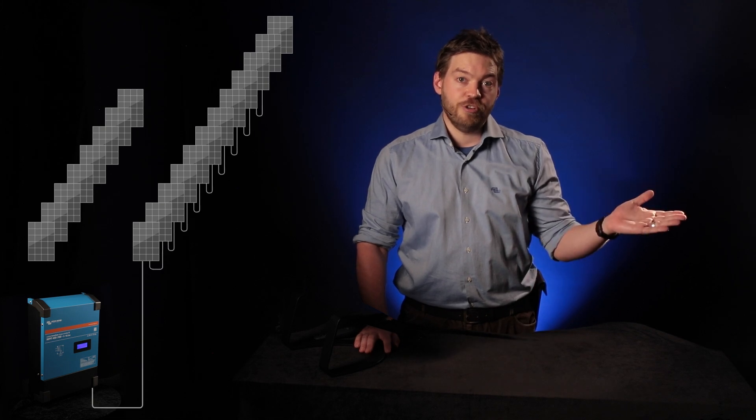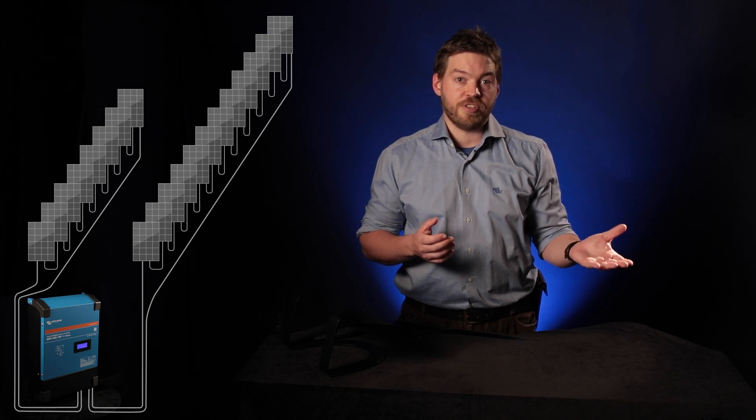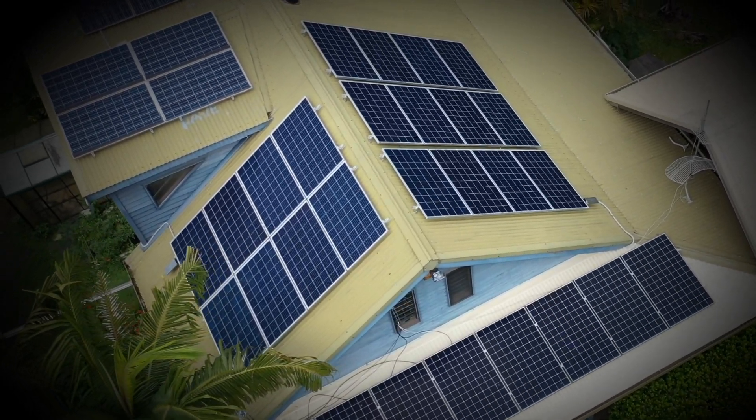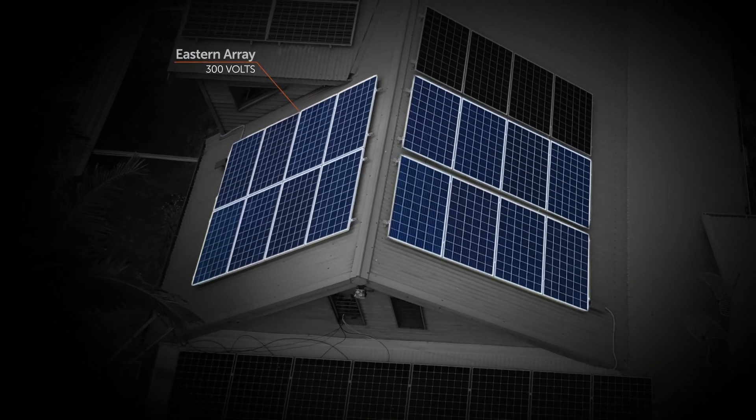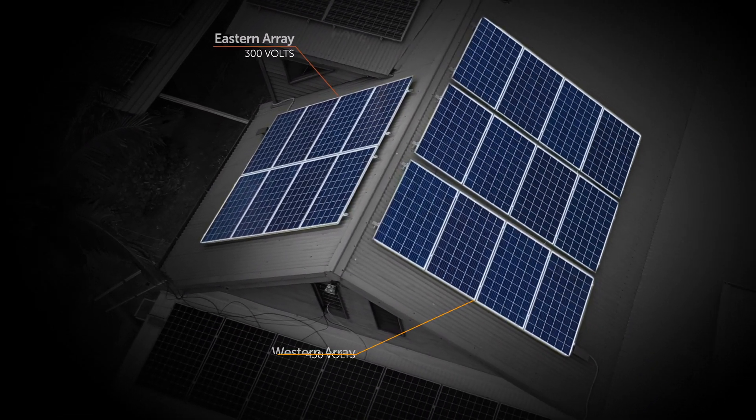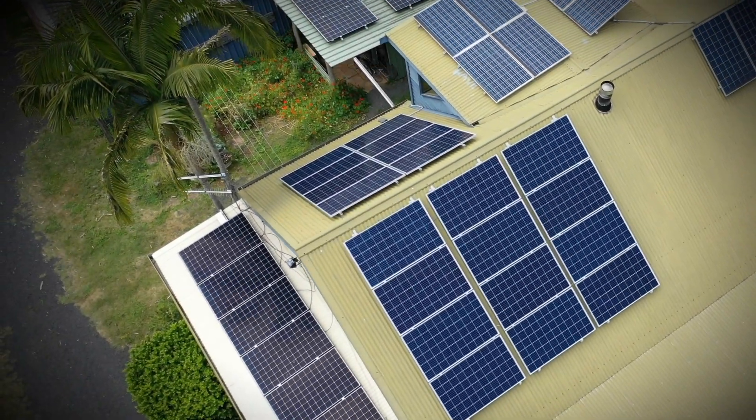Another big new feature of the MPPT RS is independent trackers. With these two separate inputs it means you can connect two different independent PV arrays. For example one on the east face of a roof and one on the west face of a roof. These can be strung up in different voltages as long as they both comply with the specifications. In our system example here we've got an eight panel array on one side operating at around 300 volts and a 12 panel array on the other side operating around 430 volts. This allows maximum output as we can capture morning light and afternoon light.